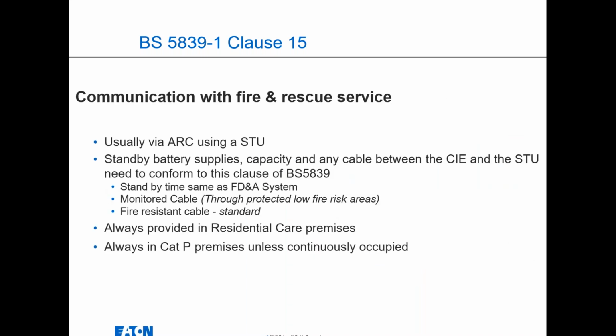Sometimes systems that have alarm receiving centers or report straight to fire and rescue services have standards they need to comply with, and the equipment needs to conform to them. Generally, they're always provided in residential care homes and also in category P systems. So if you've got a P system only, you need to have an off-site monitor of that if it goes into fire.